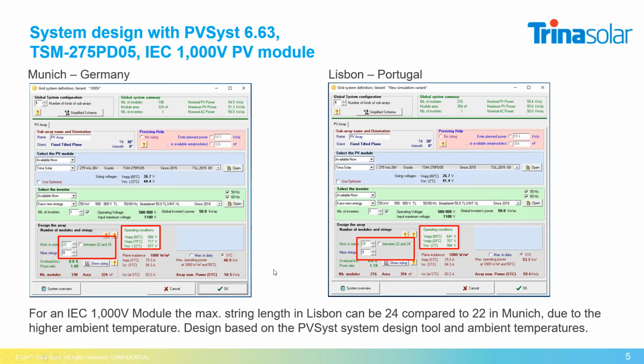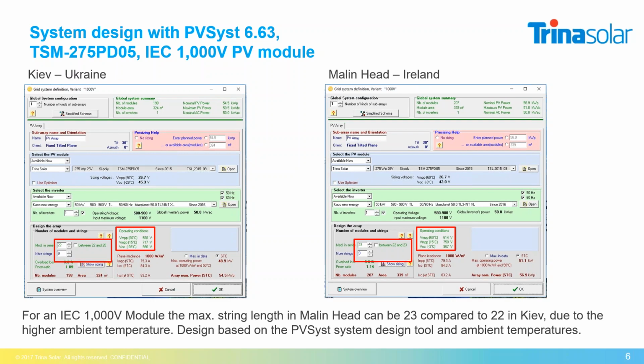Even if there are certain safety margins, and the material is also selected to be able to get the certification for 1000 volt, it doesn't mean that you can exceed it, especially if you want to follow the technical rules, as I said here with the 1000 volt. If you now take a look at Ukraine, at Kiev, you can see that the string length is also 22, and if you look at Ireland, at Malin Head, it's 23 modules within one string.